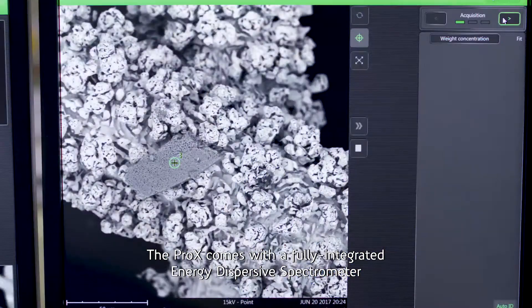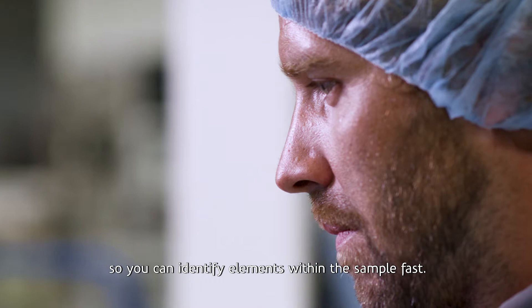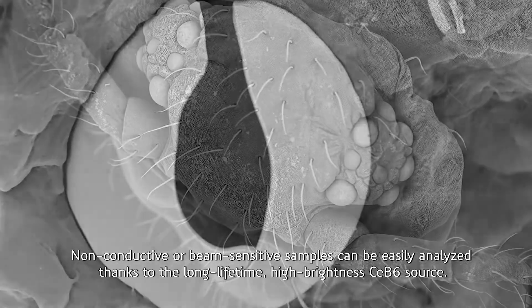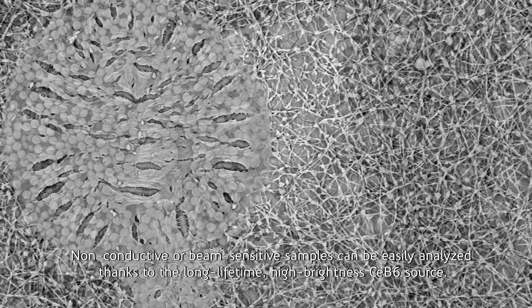The Pro-X comes with a fully integrated energy dispersive spectrometer so you can identify elements within the sample fast. Non-conductive or beam-sensitive samples can be easily analyzed thanks to the long-lifetime, high-brightness CeB6 source.